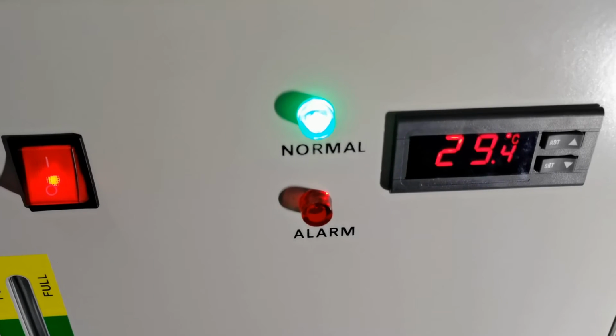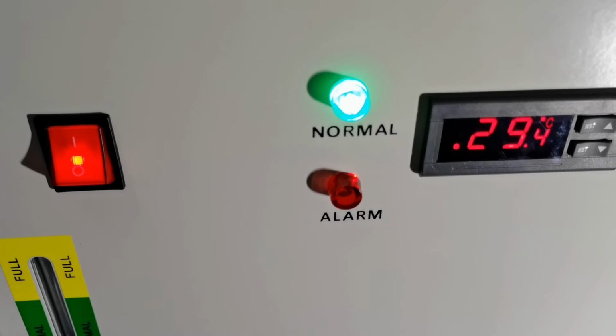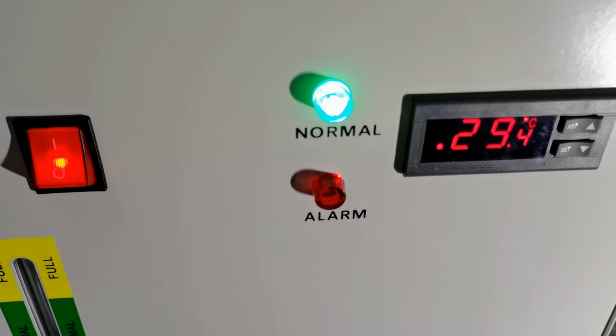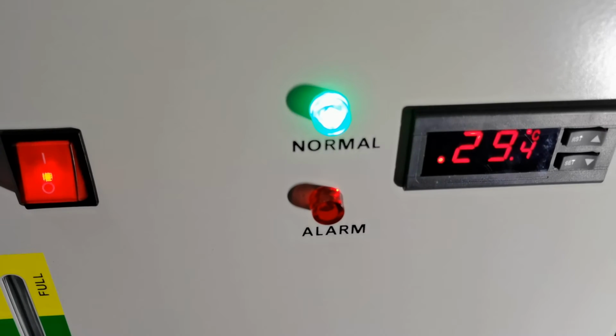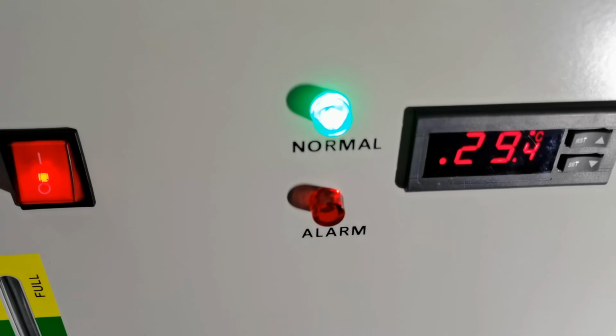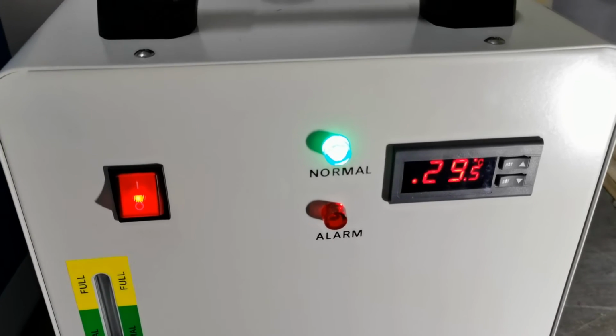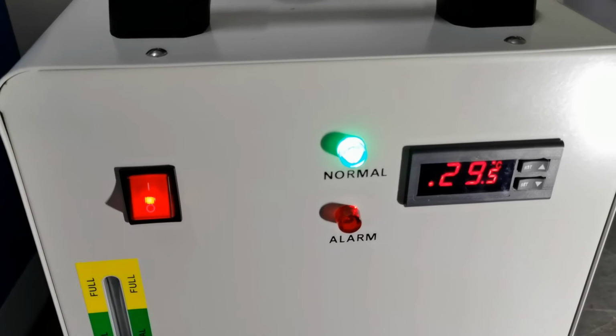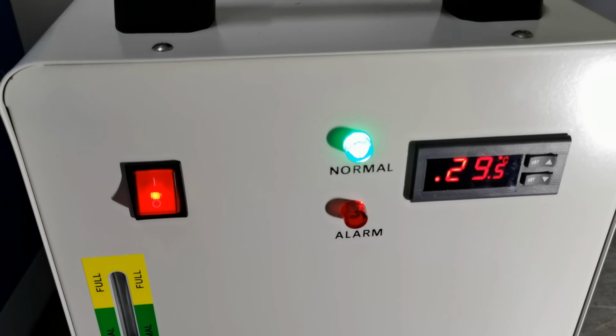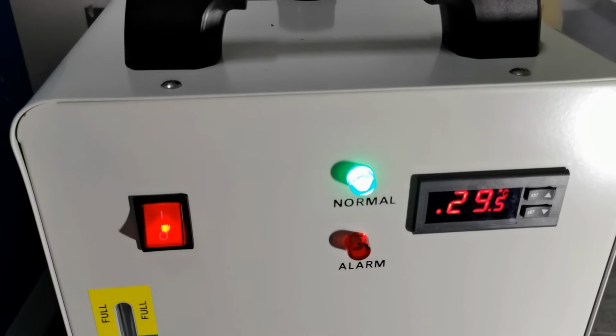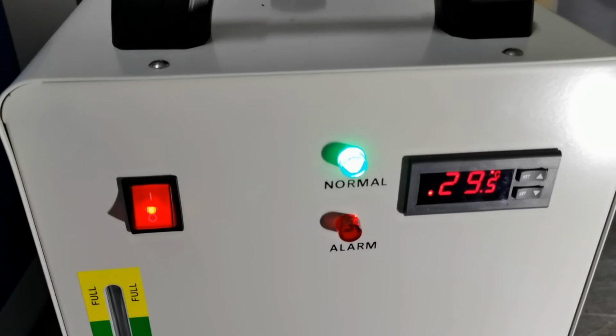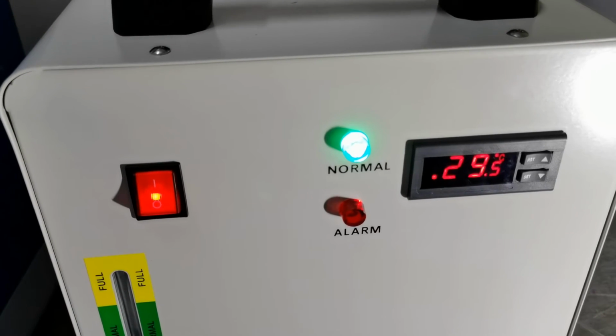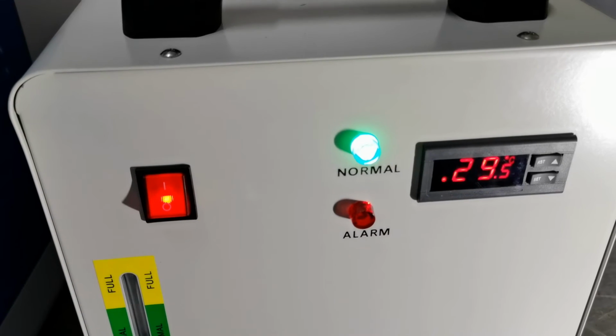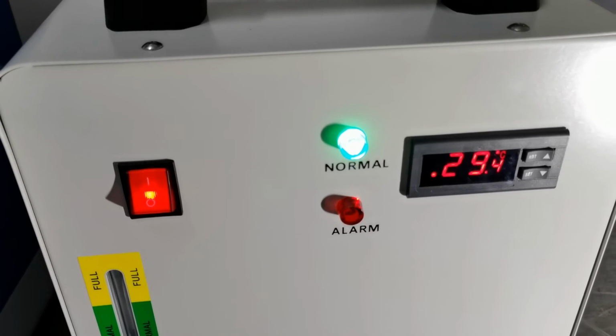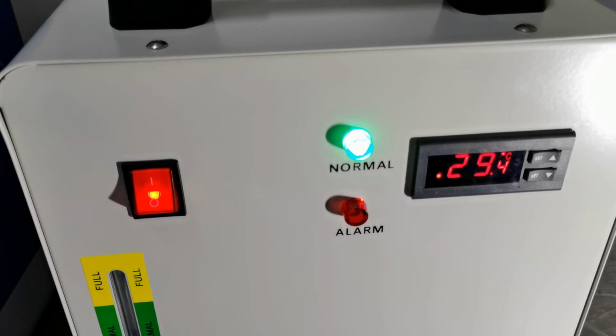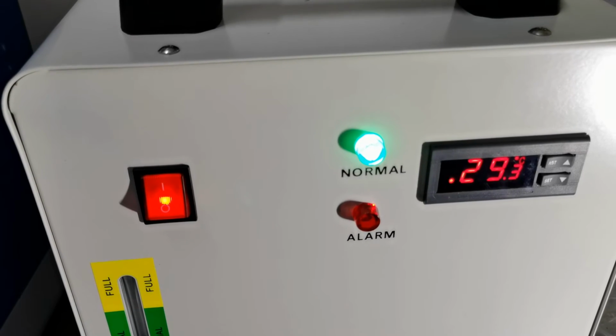The water chiller is working now to cool the temperature of the coolant in the laser tube. A tip to highlight: in the normal process, we will wait 8 to 10 minutes for the temperature to go down, and also we need this waiting to make sure the air bubbles inside the laser tube are exhausted.